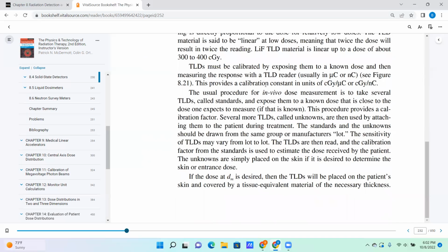So TLDs must be calibrated by exposing them to a known dose and then measuring the response, in units of centigray per microcoulomb or centigray per nanocoulomb. The usual procedure for in vivo dose measurement is to take several TLDs called standards and expose them to a known dose that is close to the dose one expects to measure. This procedure provides a calibration factor. Several more TLDs called unknowns are then attached to the patient during the treatment. The standards and the unknowns should be drawn from the same group or manufacturer's lot. The sensitivity may vary from lot to lot.